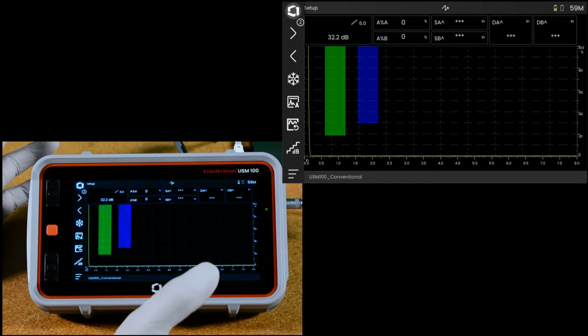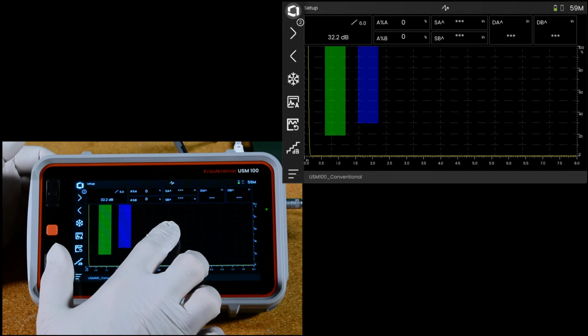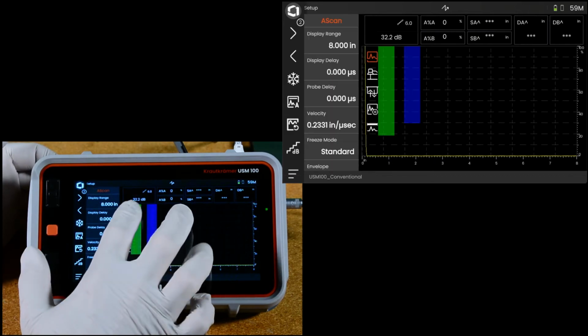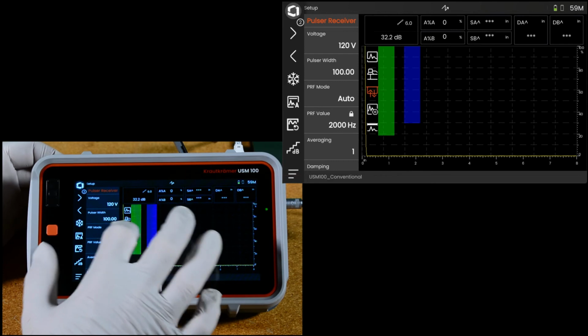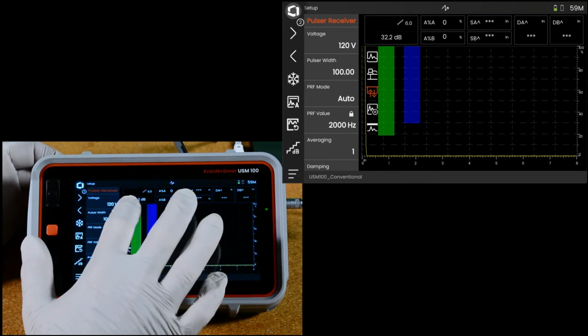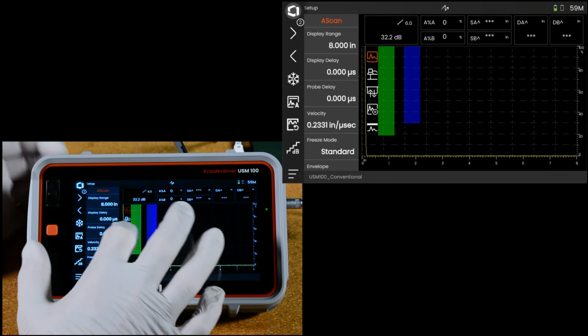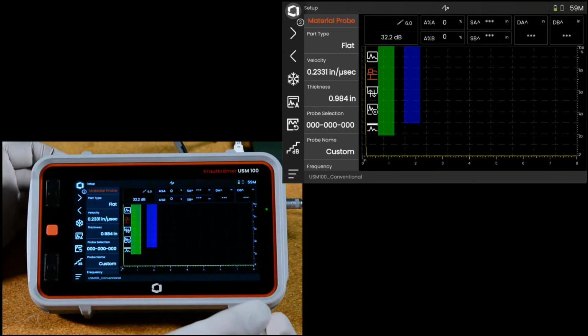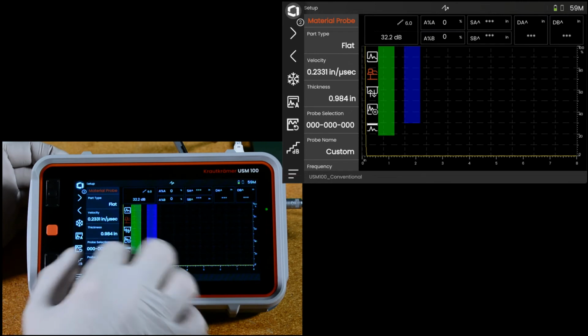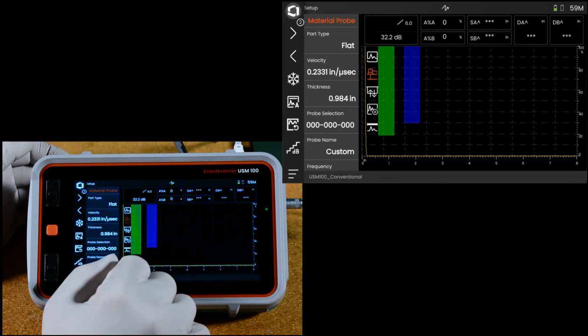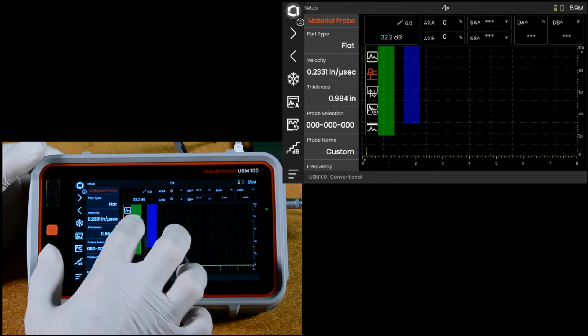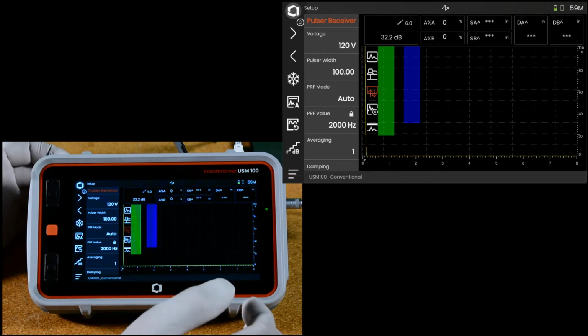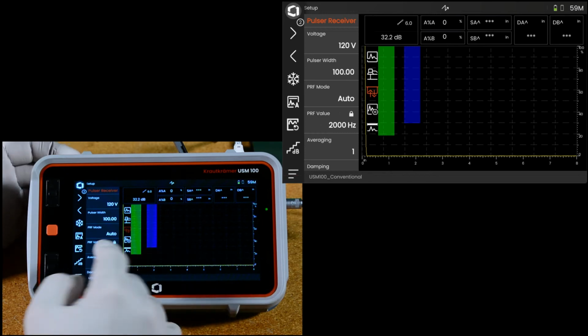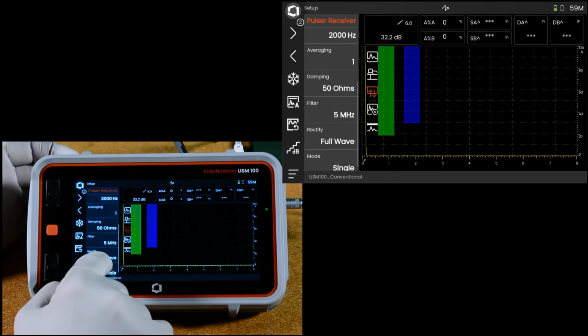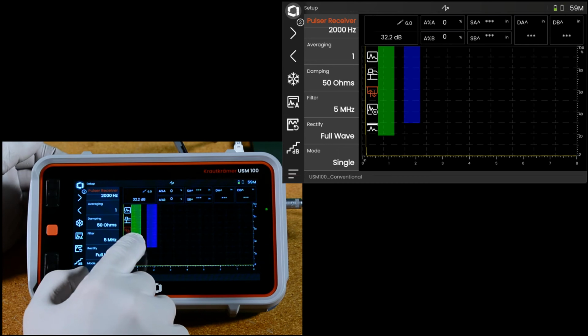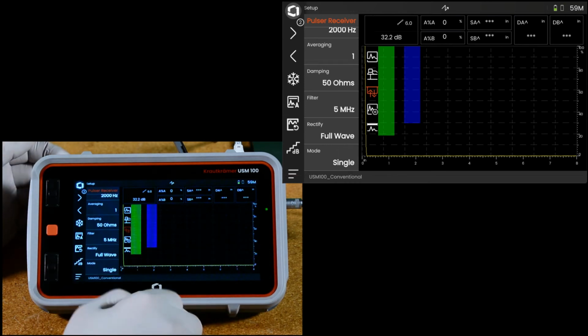They only appear for about 2 seconds, but if you tap, select one of them, now the menus stay up for as long as the menu is open. Going top to bottom, we have A-scan menu. Next one down is probe and material. So these are all parameters that describe the material that you're inspecting and the probe itself. Below that is the pulser receiver menu. Pulsar voltage, pulse width, rep rate, damping, filters, all the normal selections you would expect in ultrasonic controls.